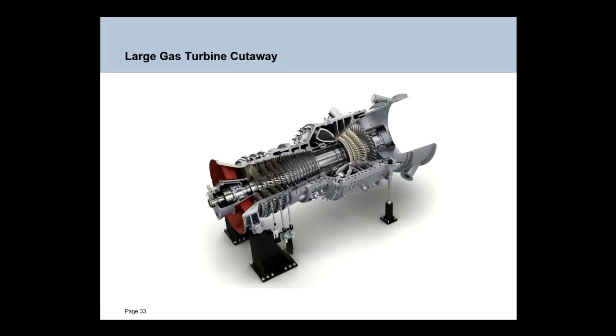So this is a picture of a large utility. This is, I think, about a 500 megawatt gas turbine. You can see here the inlet. There's a 17-stage compressor here, okay, with about 24 burners in an annulus around the turbine. Those burners burn into this combustion chamber. It's a circular combustion chamber. And then the gas is expanded through 4 rows of gas turbine blades and then out of the exhaust.